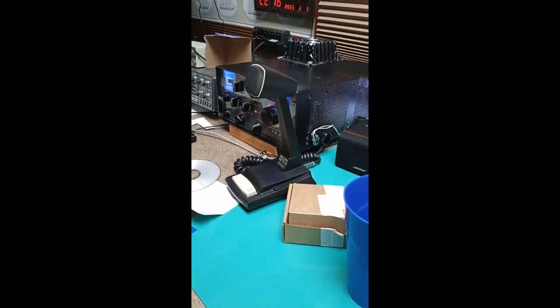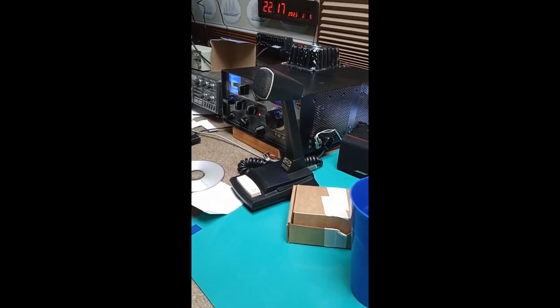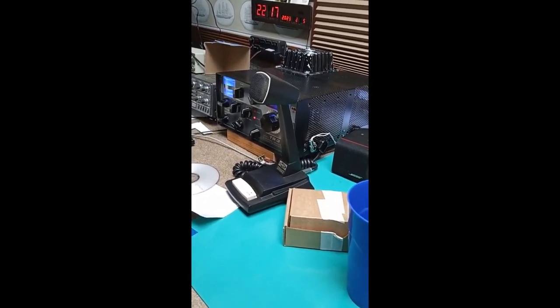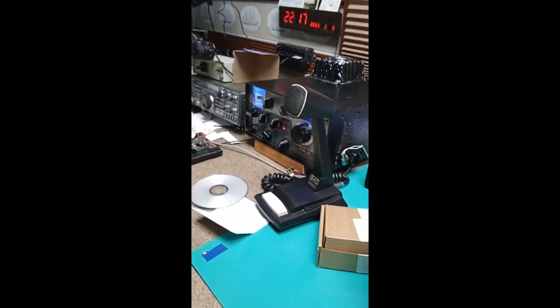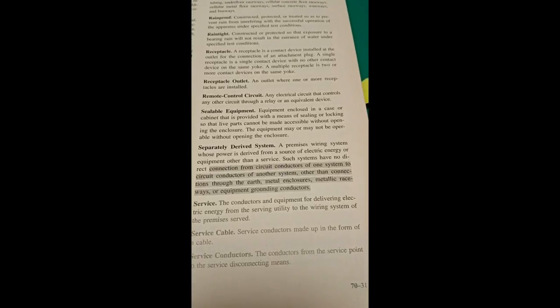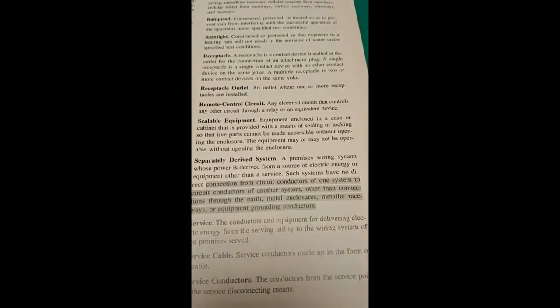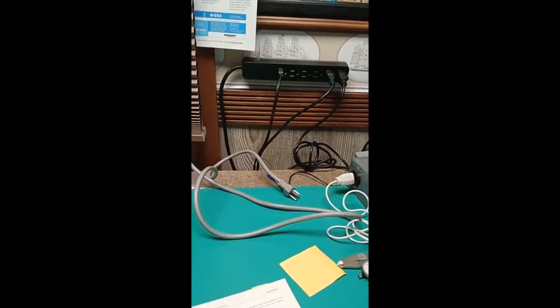It is a dangerous shock hazard to ground that for lightning, because lightning happens outside and it hits the yard, it energizes the ground wire and energizes the cabinets on these radios. Dangerous. Service equipment definition in Article 100, derived from the idea of service, the conductors and equipment for delivering electric energy from the serving utility to the wiring system of the premises served. And that implies wiring something in, not plugging it in a convenience outlet. A radio transceiver is not service equipment.